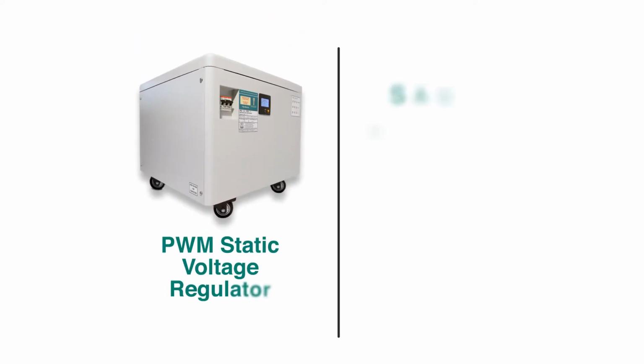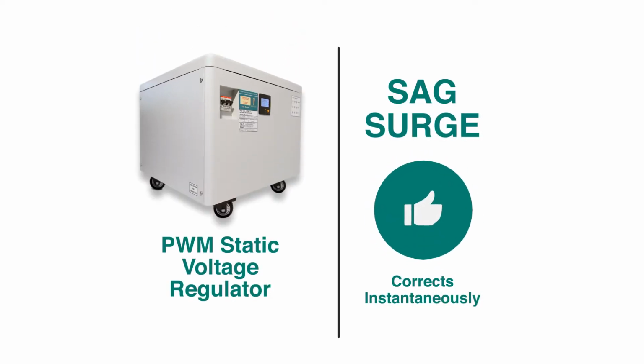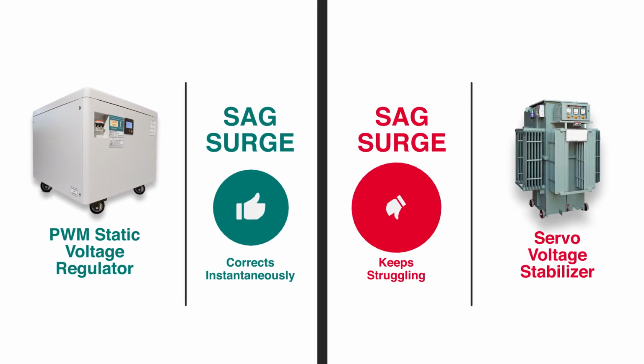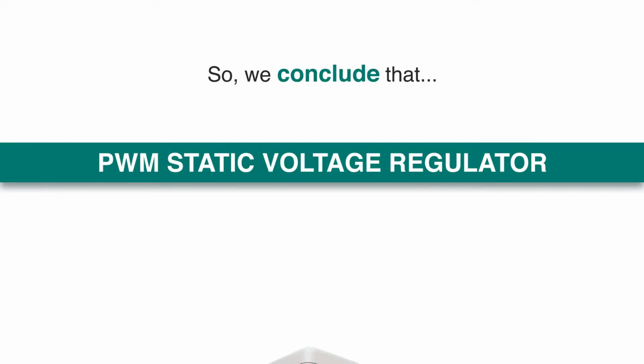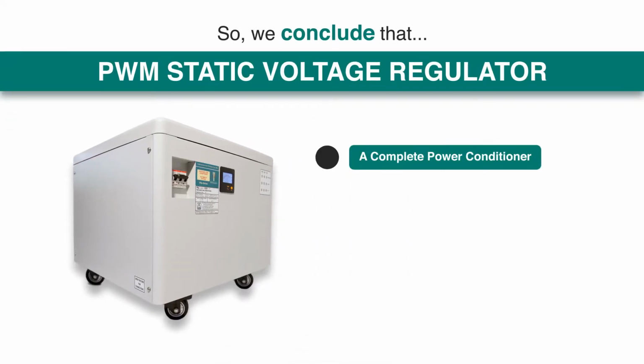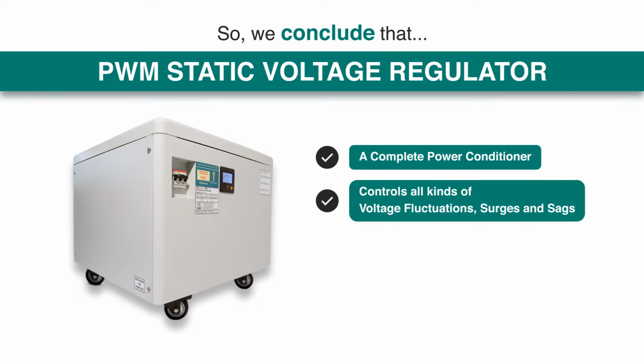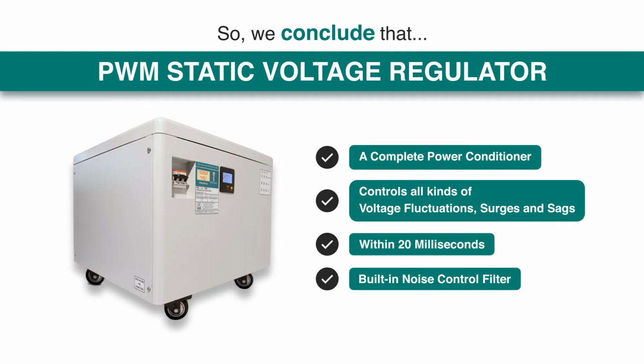So, as we can observe, the static voltage regulator would correct a surge or sag instantaneously, while servo voltage stabilizer would keep struggling. So, we conclude that the static voltage regulator is a complete power conditioner, which controls all kinds of voltage fluctuations, surges, and sags, all within 20 milliseconds, that is, one waveform. In addition, it also has a built-in noise control filter.